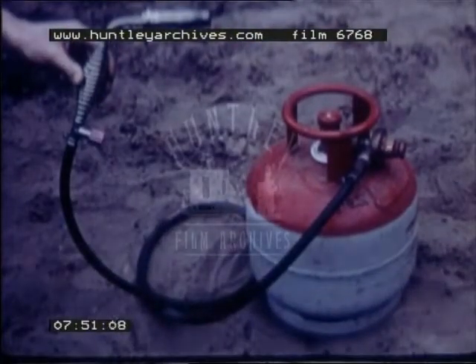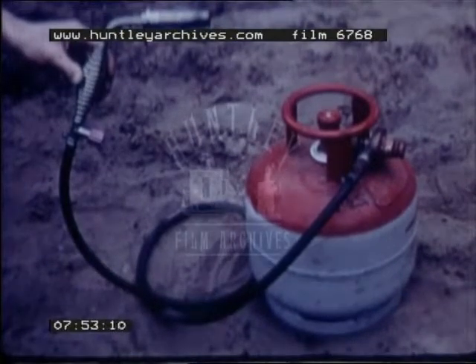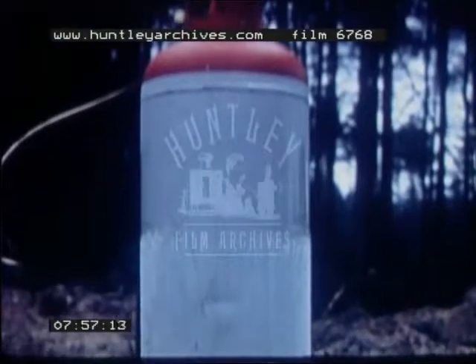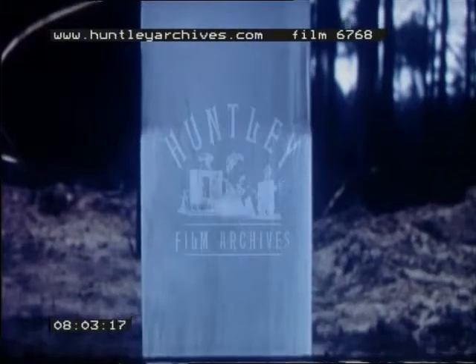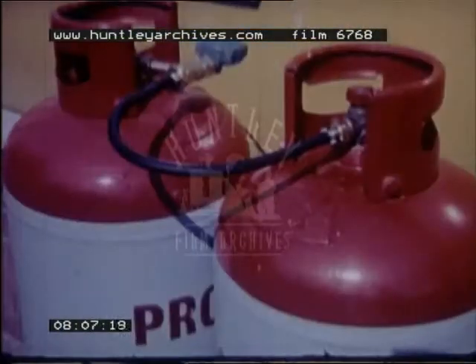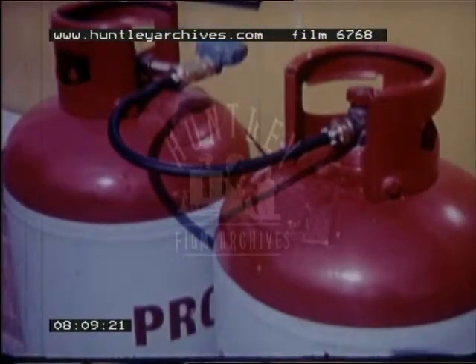You have your system ready for use. Now let's see how to use it safely. An all too frequent sight is a cylinder in use half covered in frost. Gas is being drawn off at too great a rate. The cure is simple. Where possible, use a bigger cylinder or, as in this case, manifold two cylinders together.